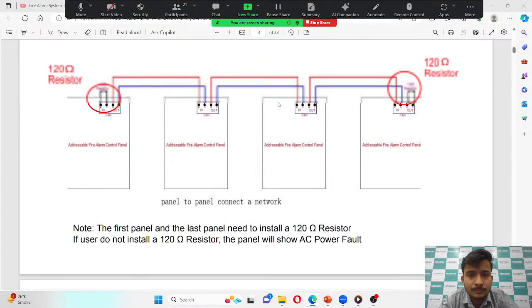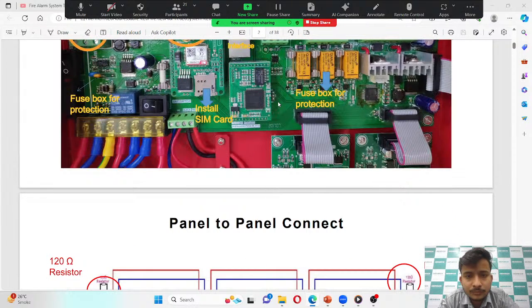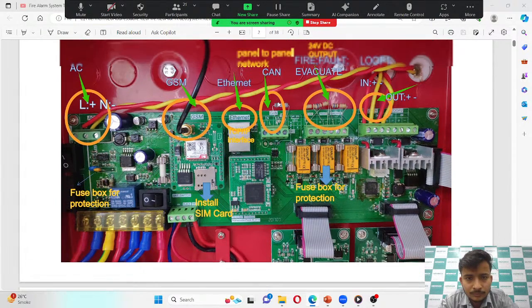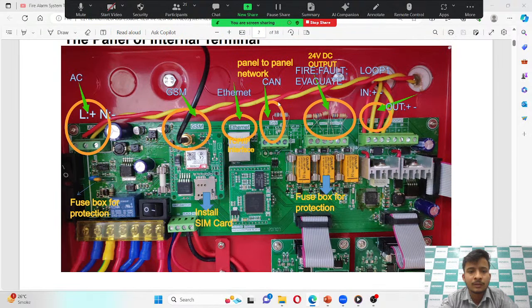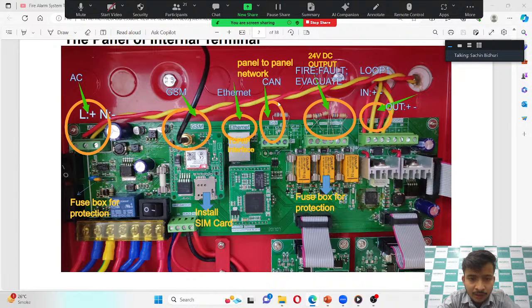Okay, sir. Then what is the approval for this? EN54? VDS, we have approval, and we have EN54 approved. Yeah, okay, sir. Our maximum length of the cable from the fire alarm panel is up to 2000 meters, which means 2 kilometers. Maximum loop capacity is 250 devices.